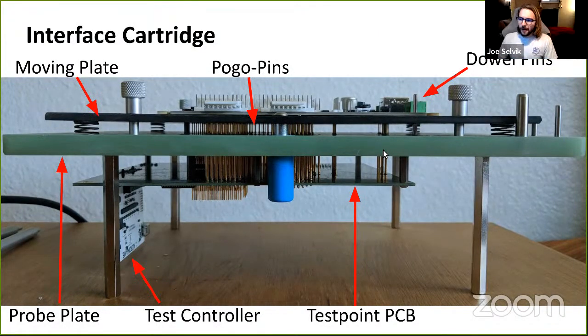No, I'd say we probably slightly prefer through-holes because they're typically larger than SMD test pads. Mechanically, if it's a spear tip going into a through-hole, that's going to be secure every time, with not much to interfere with on either end. With a pad, a spear tip might bounce off it a little, but as long as the pad is the right size and spaced correctly, they're basically the same reliability to probe.